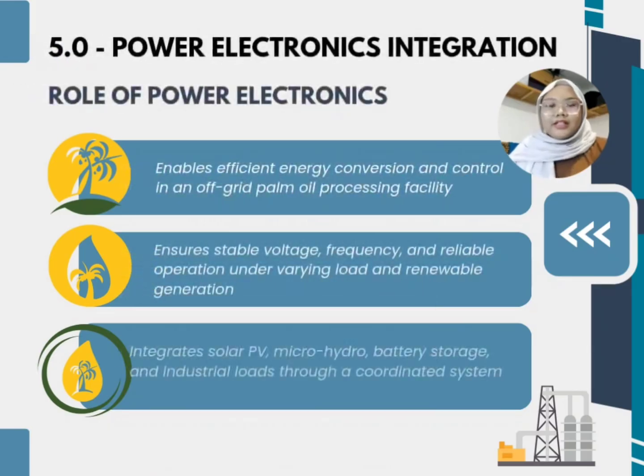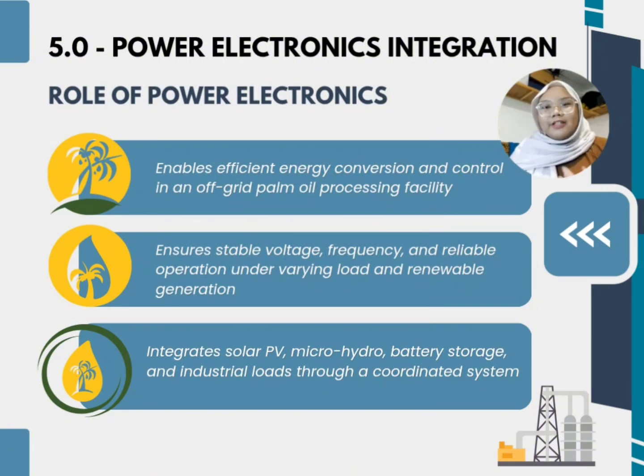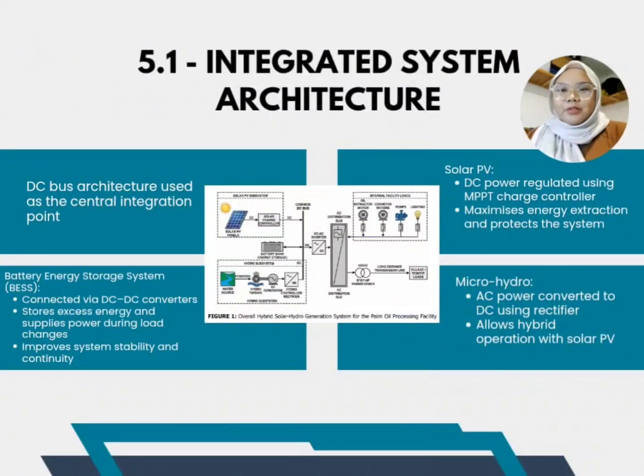Thank you. Next is about power electronic integration. Power electronics enable efficient energy conversion and control in this off-grid palm oil processing facility. They are important to maintain stable voltage, stable frequency, and reliable operation when the load and renewable energy generation change. This system uses a DC bus architecture as the central integration point. The solar PV system generates DC power and is regulated using an MPPT charge controller to maximize energy extraction and protect the system. The micro hydro system generates AC power, which is converted to DC using a rectifier to allow hybrid operation with solar PV.